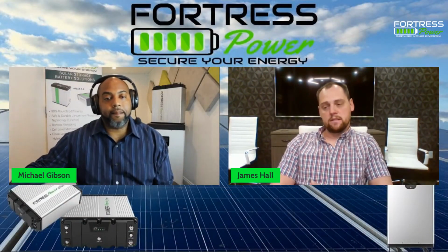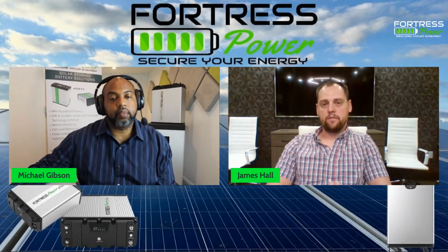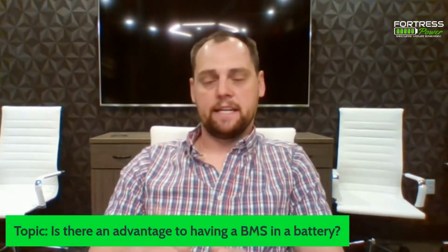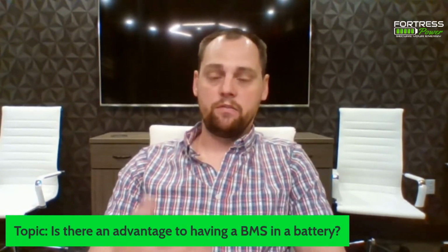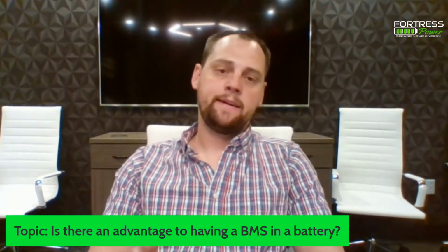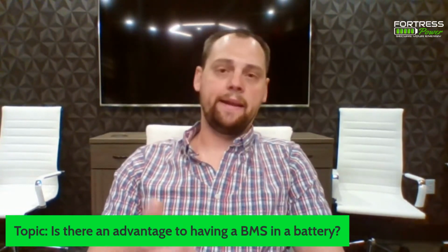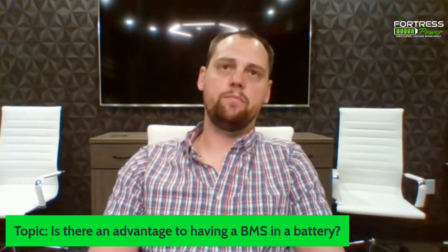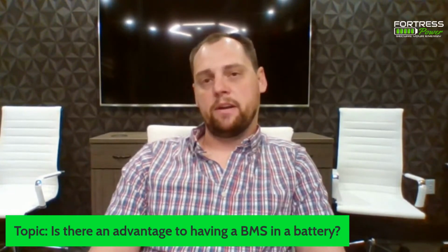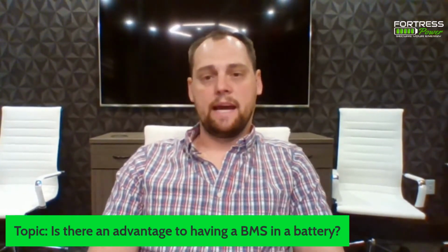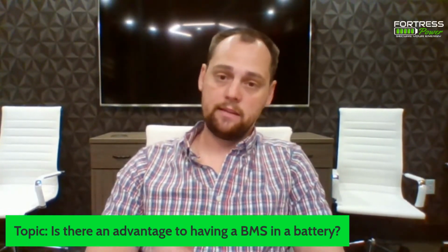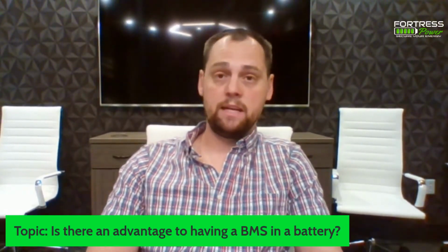As far as batteries and BMSs are concerned, it's imperative that a lithium battery has a BMS in my eyes. That's what makes it such a robust solution—the battery management system can monitor the lithium battery internally and essentially say no when the battery is getting to a point where it could be damaged. In a conventional system with lead acid batteries, you're relying on the inverter system or generator to step in if the batteries are getting to a point where they could be damaged. With a lithium battery, that's done on the battery level, which is a super important consideration, since lithium batteries that are overcharged are immediately damaged essentially.